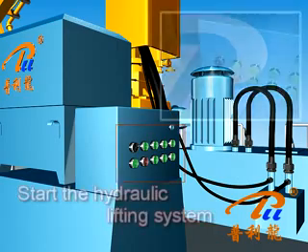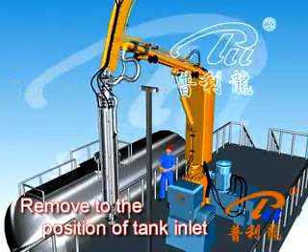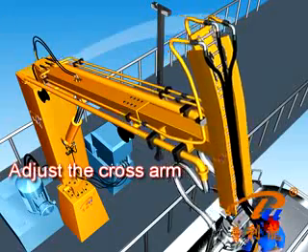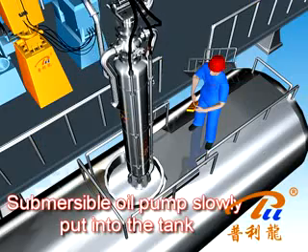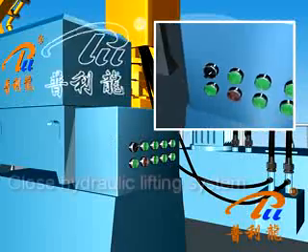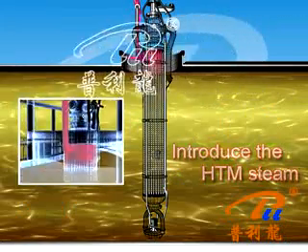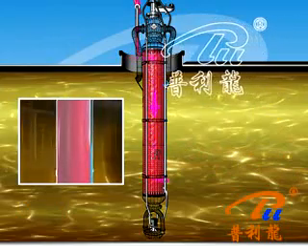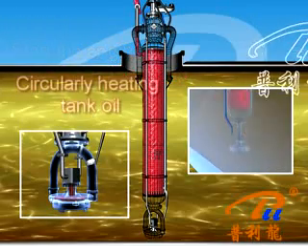Switch on and start the hydraulic lifting system. Raise the cross-arm and move to the position of the tank inlet. Adjust the cross-arm and place the submersible pump into the tank. Then close the hydraulic lifting system. Open the steam valve and introduce the HTM steam. Start the engine of the submersible pump, circularly heating the tank oil.